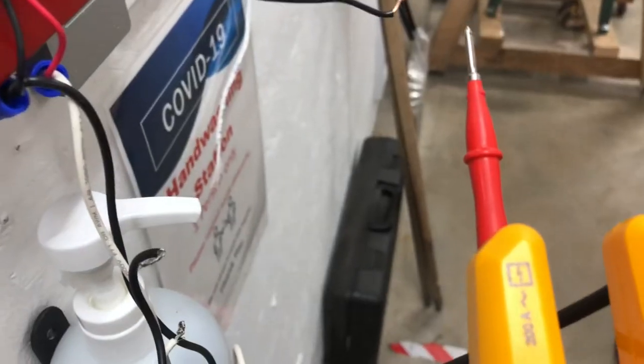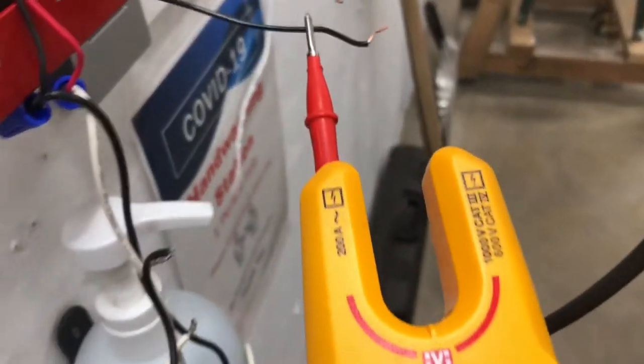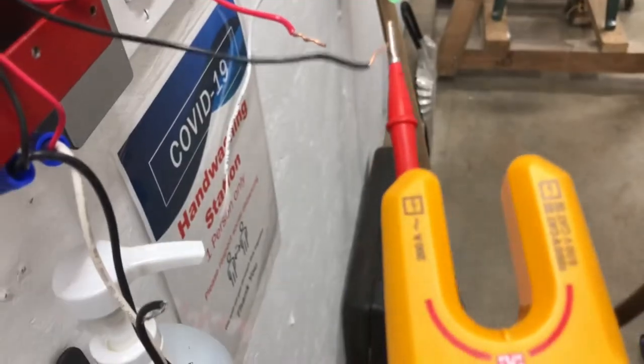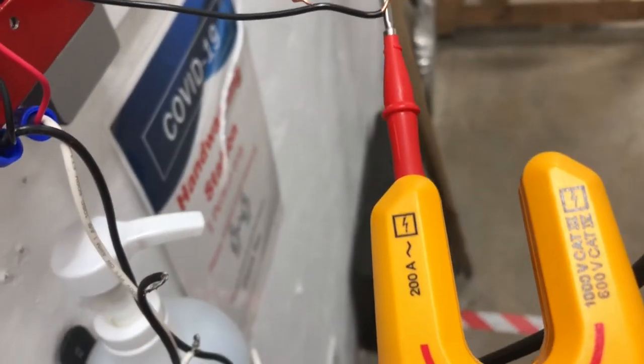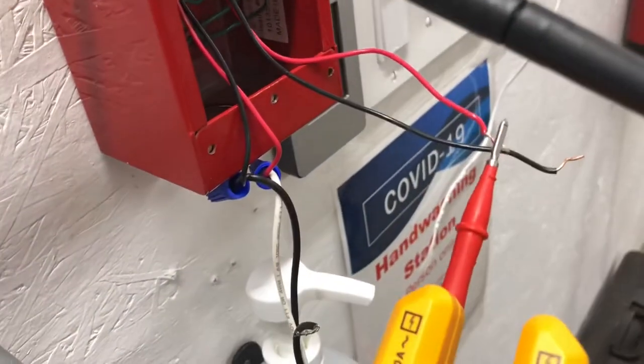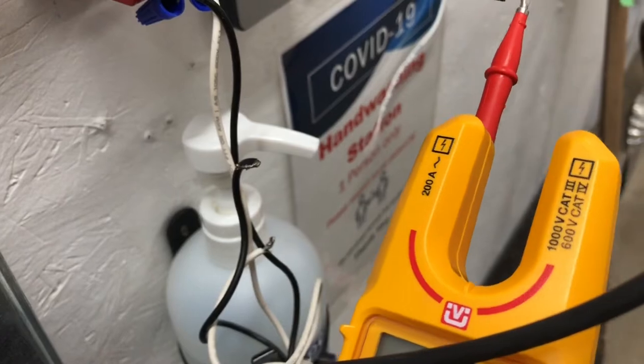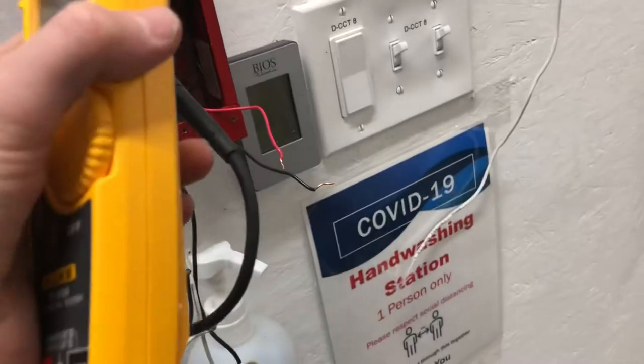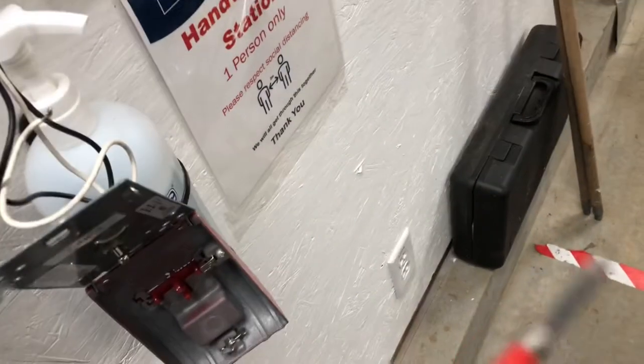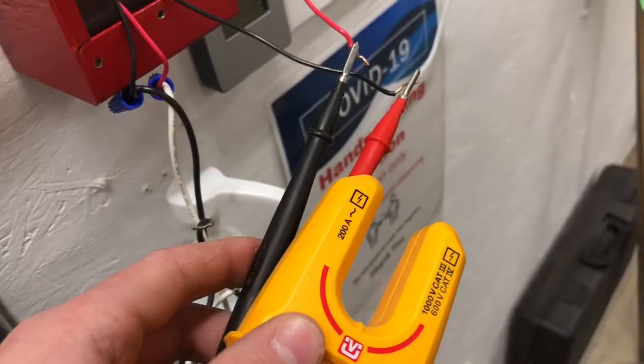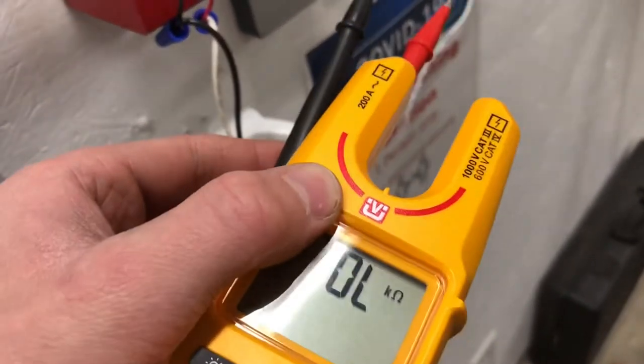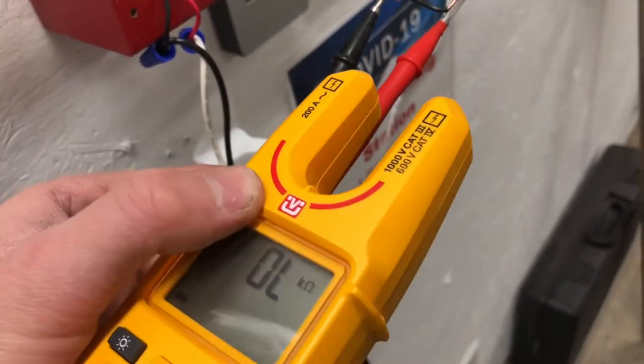Assuming you kept doing this at every device or every other device and you kept seeing the same resistance on your red and the same very low resistance on your black. Now, let's say you get to one device, which I've taken out my ground fault, where you get open line on the red and open line on the negative. However, you go between the two. If I can get your meter in there like this. Sorry, I had it for a second and now it went away.